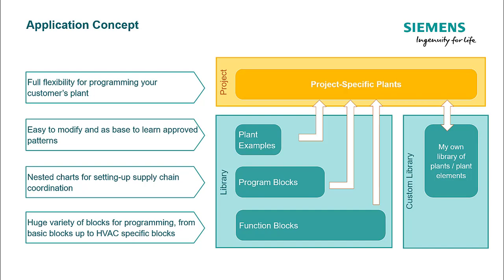What are plants? A plant in the programming editor consists of all required function blocks to control plant components for an HVAC plant or partial plant. A plant can have the following components: input blocks like sensors and switches, and function blocks with programming logic to calculate values for the output blocks based on the values of the input blocks.